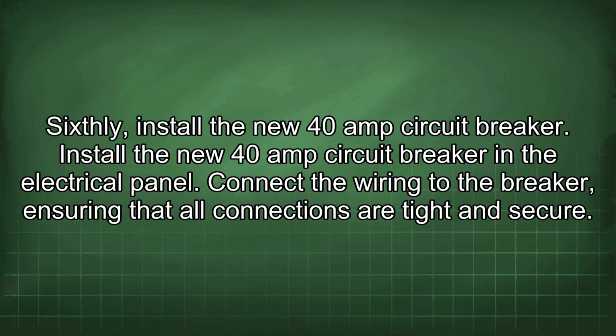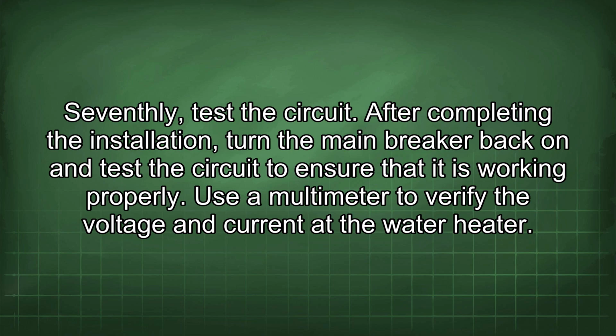Sixthly, install the new 40 amp circuit breaker. Install the new 40 amp circuit breaker in the electrical panel. Connect the wiring to the breaker, ensuring that all connections are tight and secure. Seventhly, test the circuit. After completing the installation, turn the main breaker back on and test the circuit to ensure that it is working properly.